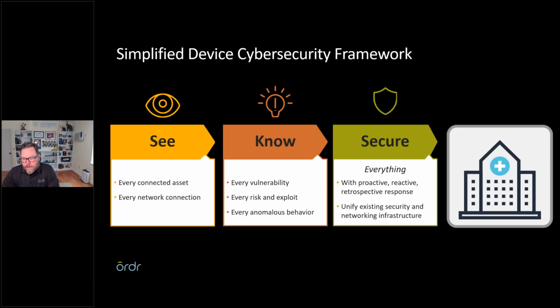And then knowing about those devices, know what vulnerabilities are out there, know what risks and exploits are available for those devices, and then know about the behavior of those devices. So knowing what your device is supposed to do, monitoring what that is, and then being able to react if that device acts outside of its known behavior. And then secure, using the tools that we have already available to us to secure the devices, because the manufacturers, once they stop supporting the device, are no longer going to upgrade the operating system. They're no longer going to be able to provide additional support for devices that are no longer supported by the operating system manufacturer.